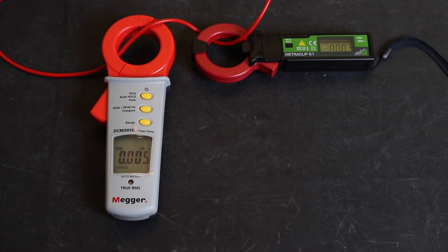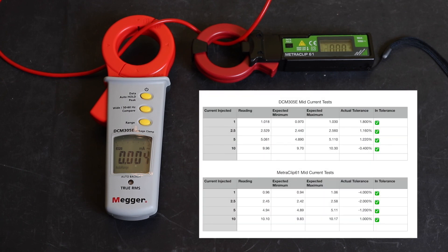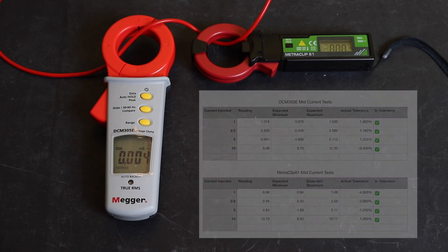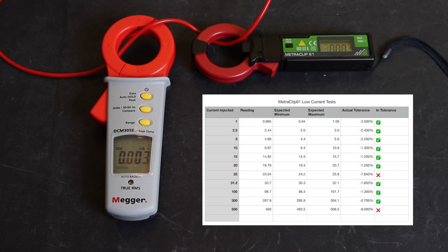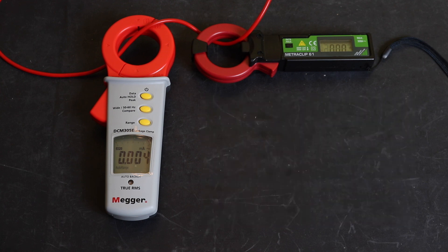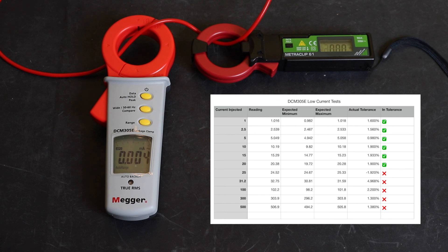This is the results table for the mid-range of currents from 10 amps down to 1 amps. You can see there I've got green ticks across all the readings there. They are all within tolerance, so no problems there whatsoever. I'm going to put this next table up. This is for the low milliamps range. So this is 500 milliamps down to 1 milliamp. You can see that for the Metrawatt I've got 2 readings that are out of tolerance towards the top end of the range. And then I've got actually 5 readings that are out of tolerance for the DCM305E.